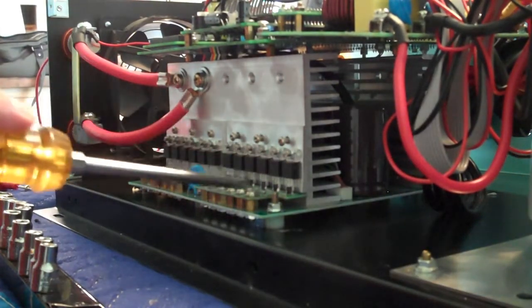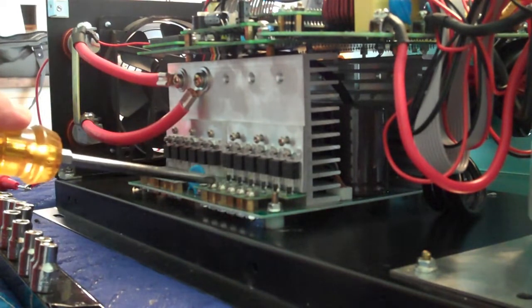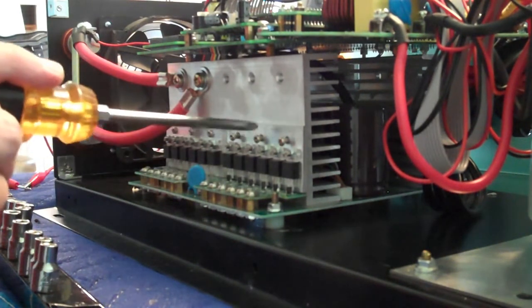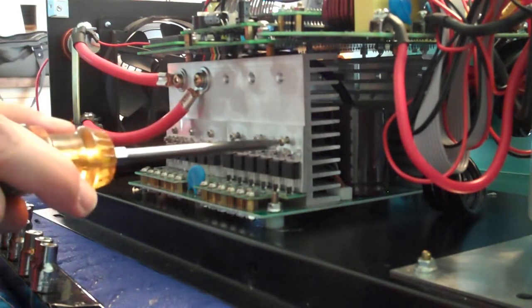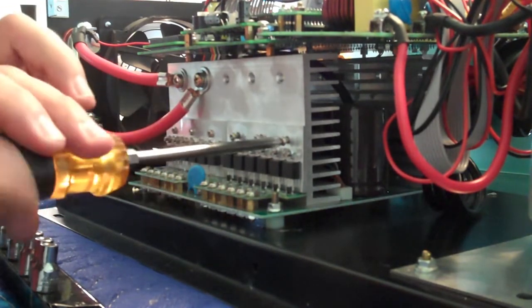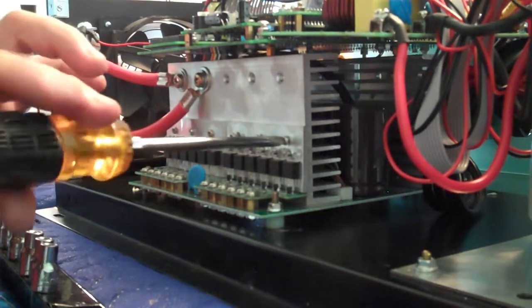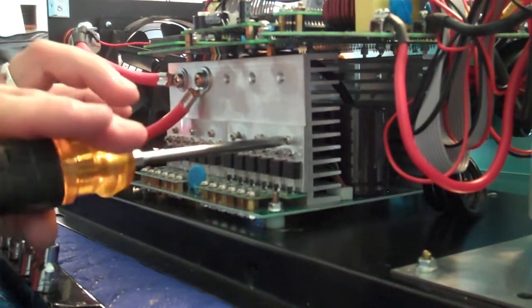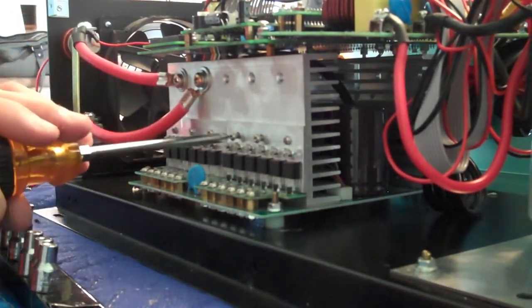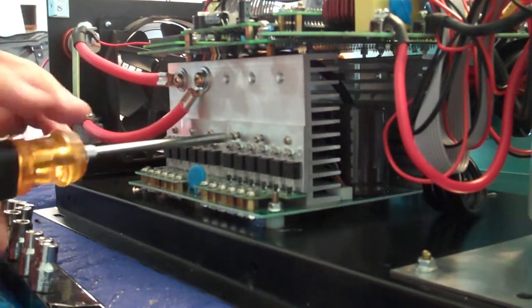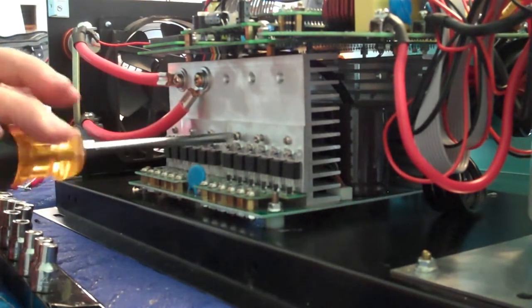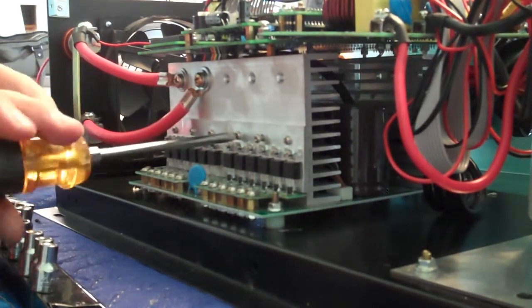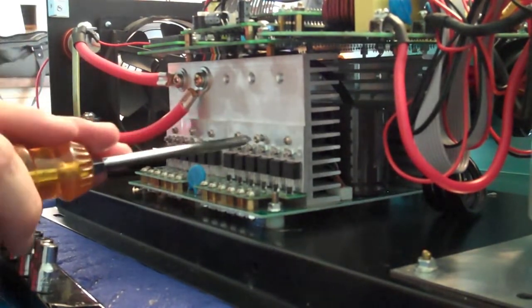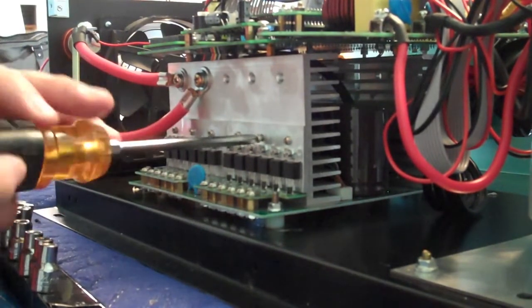All right, I tightened these 5 power connectors and the signal or switching connector first. These guys I just had loosely in there to kind of hold it in place. And now that it's in there, I'm going to tighten the top guys nice and tight. There's a decent amount of clearance on these holes, so it can kind of align on its own a little bit. The tolerances aren't terribly precise, but you do want to make sure this is nice and tight to that aluminum plate on the back so heat can get transferred out and dissipated.